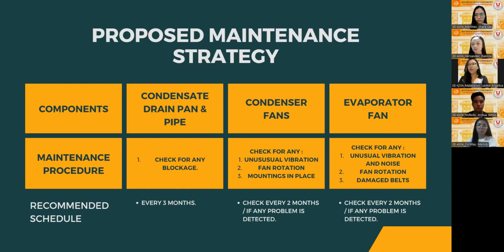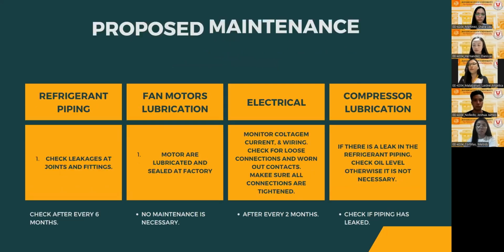For the condenser fan, check for any unusual vibration and noise. Check that mountings are in place. And it should be done every 2 months or as required if any problem is detected. For the evaporator fan, check for any unusual vibration and noise. Check that the fan rotation is correct and check and replace damaged belts. For the recommendation, it should be done every 2 months or as required if any problem is detected. For the fan motors lubrication, motors are lubricated and sealed at factory. Therefore, no maintenance is necessary unless the motor is open.